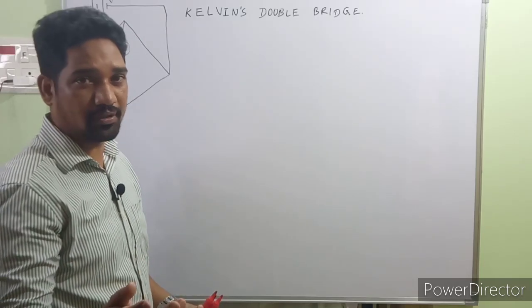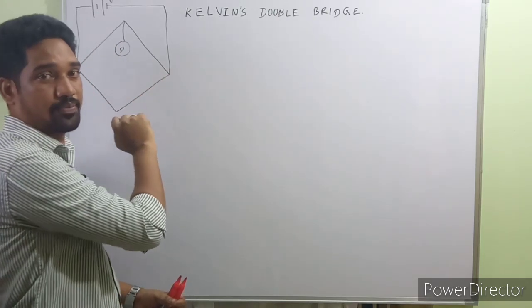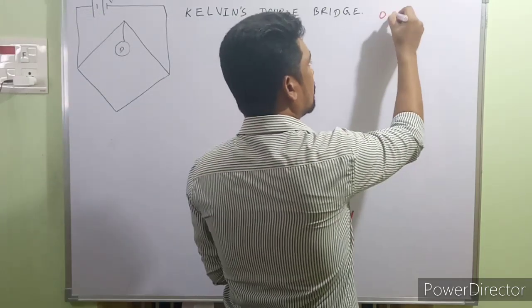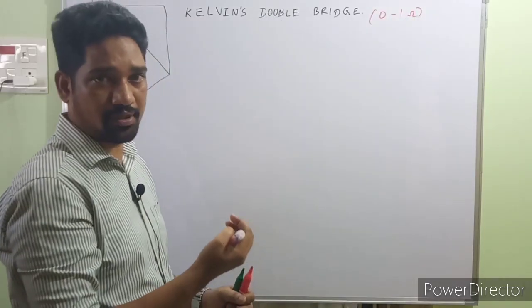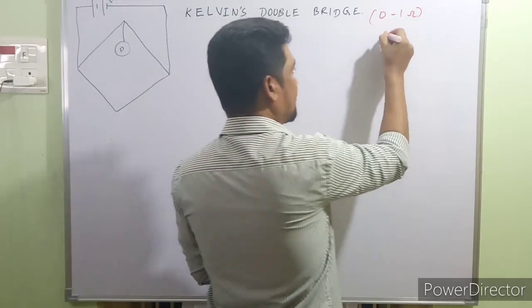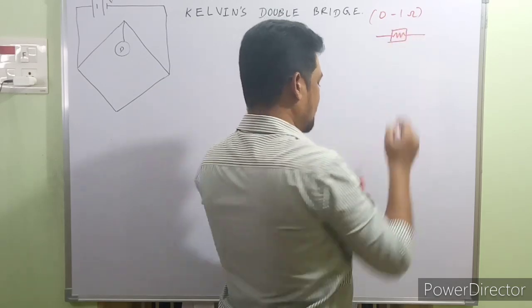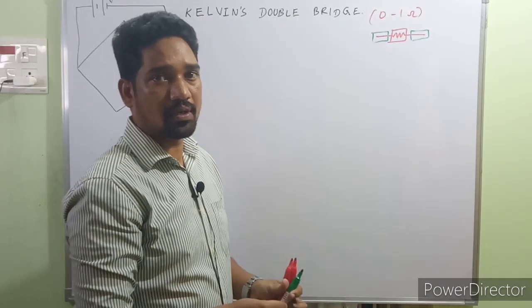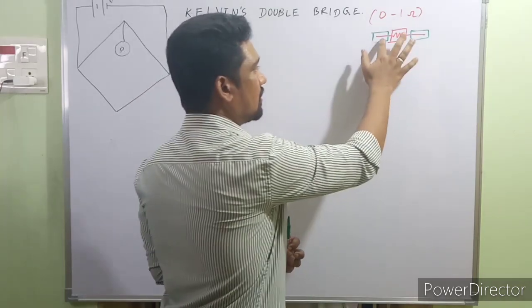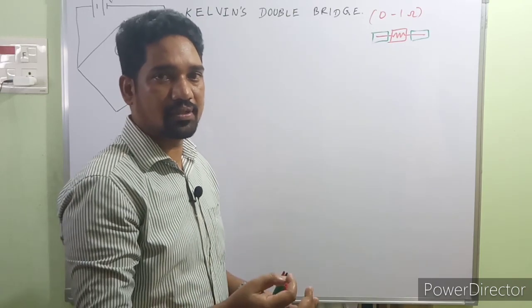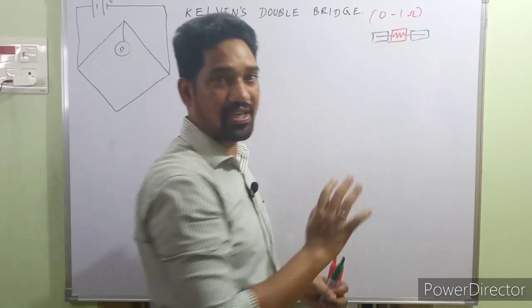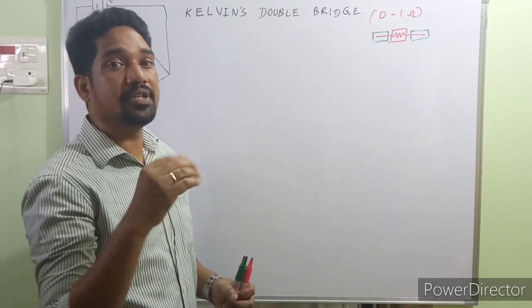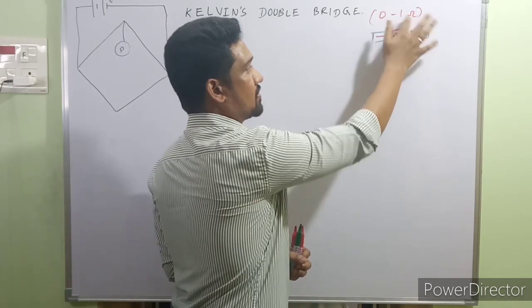So why the need of Kelvin's double bridge? It's an extension to the Wheatstone bridge. When the measurement is in the range 0 to 1 ohm, it's a very low range. While measuring unknown resistances in that range, practical resistance has connecting leads made up of a conducting metal material, introducing some significant resistance. Even these connecting leads have some resistance, which introduces significant resistance value while measuring low value resistances. The main objective of Kelvin's double bridge is to eliminate the interference of lead resistance while measuring low value resistance from 0 to 1 ohm.